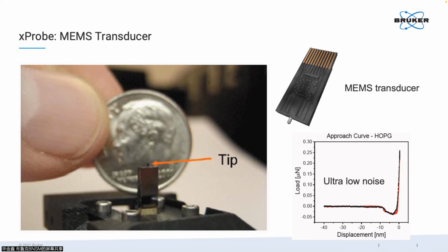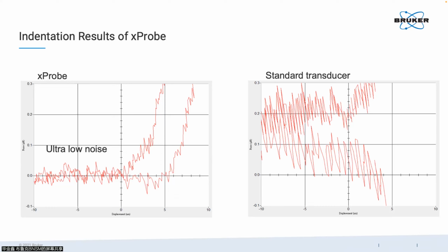This is an example of HOPG, and you can see we have a loading curve. It's very similar to the force curve of AFM application. So we have the retraction and the approaching curve. Because the deformation is exactly elastic, you can see they overlay each other quite well. I would say this data is only achieved when the noise level is very small. So the key point will be the noise. How shallow an indentation depth we are able to achieve depends on how low a noise we are able to go.